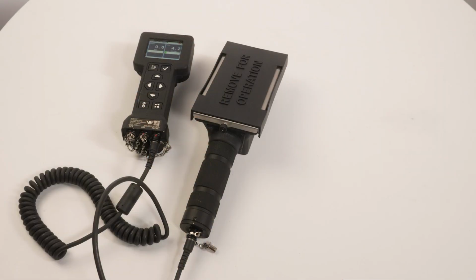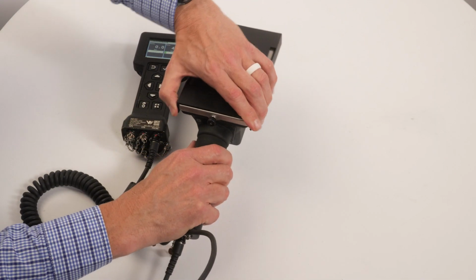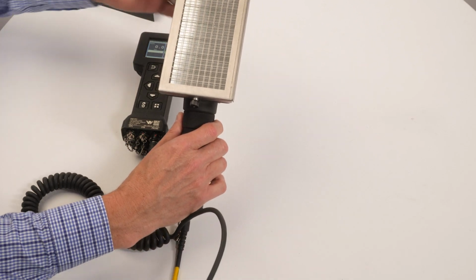In this video, training on the operation of the alpha-beta probe attached to an RDS base unit will be provided. The alpha-beta probe is used for detecting alpha and beta radiation. There are two scintillators used for the detection of radiation in this probe. A zinc sulfide scintillator, which is used for detecting alpha particles, and a thin plastic scintillator, which is used for detecting beta radiation. A protective cover is provided for additional protection of the mylar window when not in operational use. For operational use, slide cover off of the front of the probe.